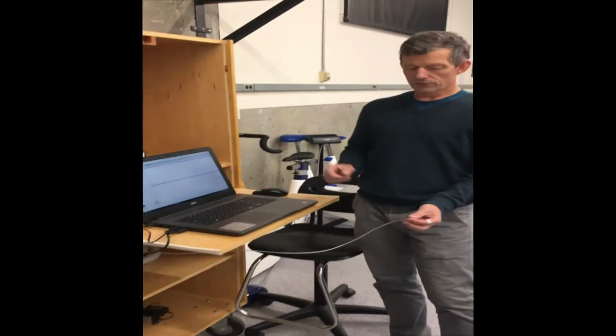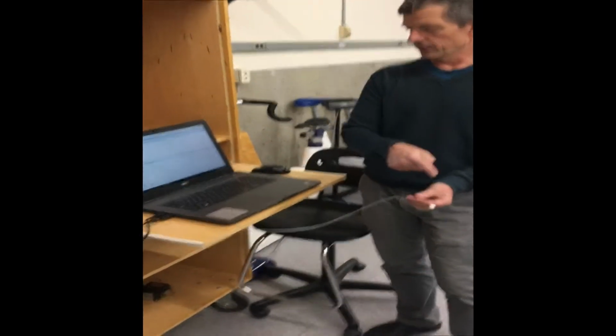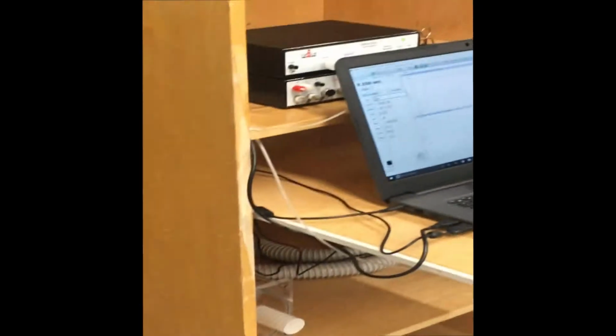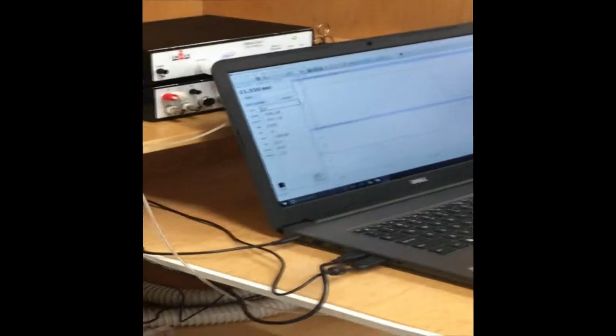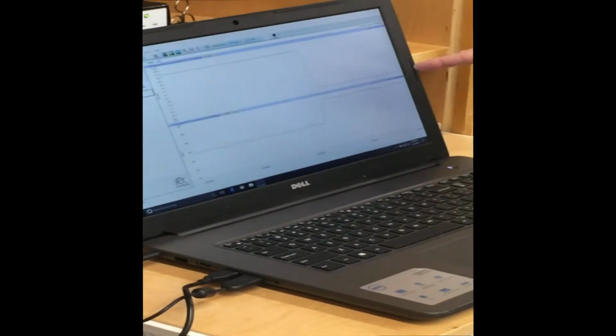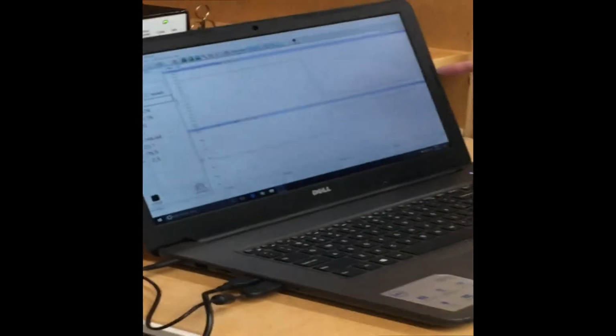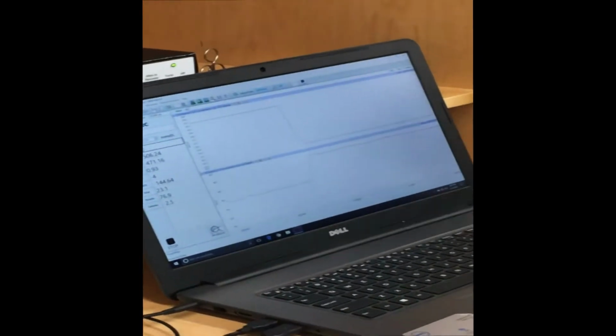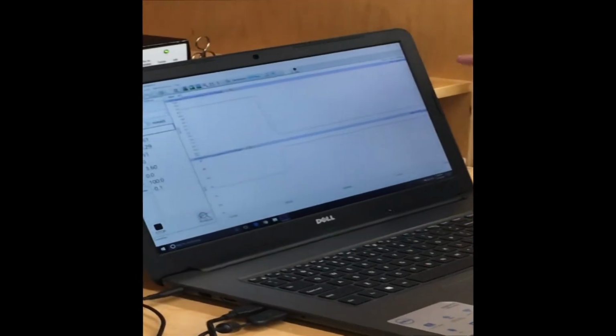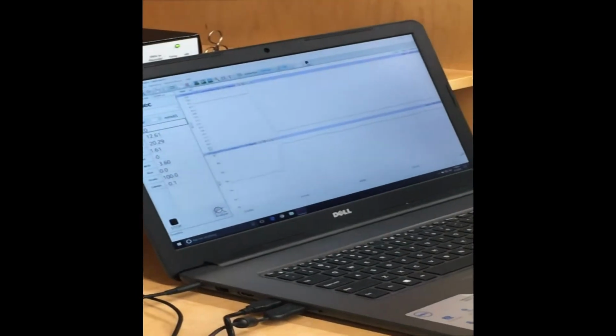Then as you click record, it is going to be continuously drawing in air and sampling that air. So right now you can see this was the calibration gas that's just passing through. This is what our value is. It's reading now for CO2 is 0.05%, and oxygen it's reading 20.84%. And you can see this is pretty sensitive and it's always doing a little bit of fluctuation.